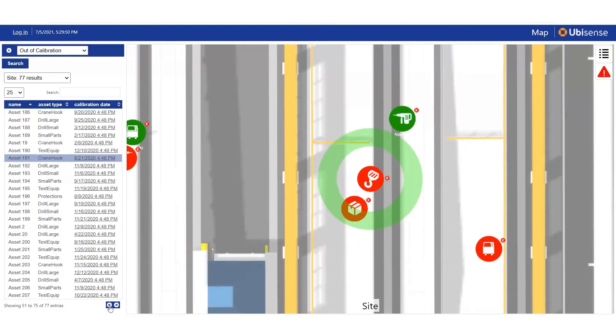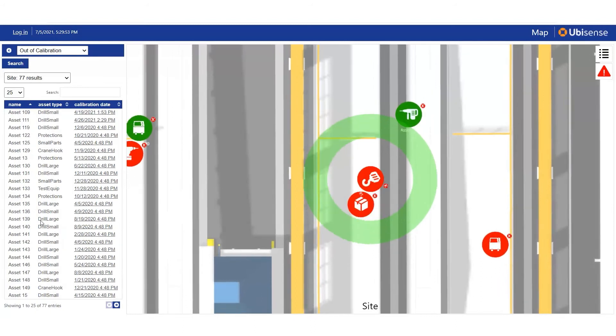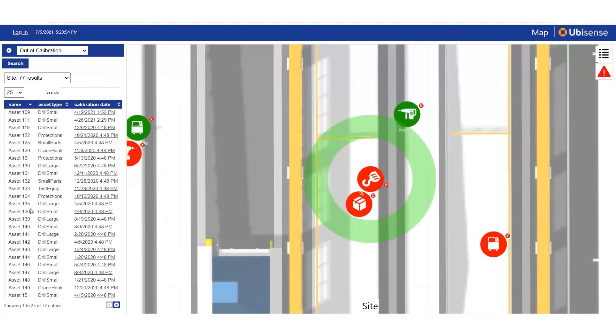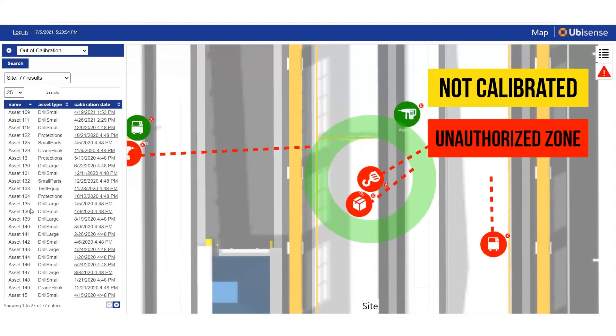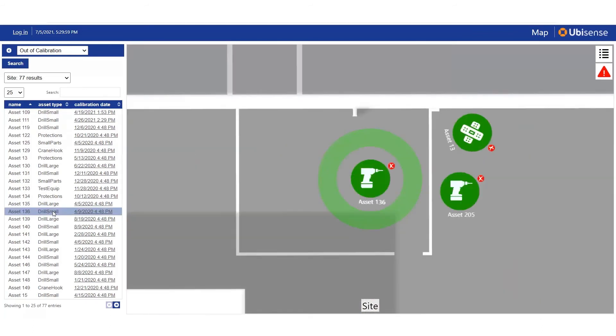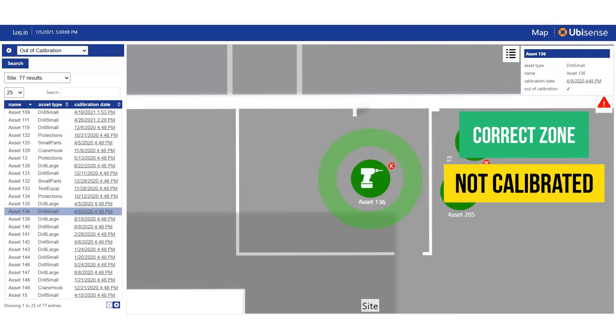Business rules can be configured to vary how assets are displayed according to location. For example, a tool out of calibration is marked with a red cross. Those in active production zones are further highlighted with a red icon to indicate unauthorised use. A tool out of calibration but correctly located in the tool store is green but retains a red cross to denote it should not be allocated.